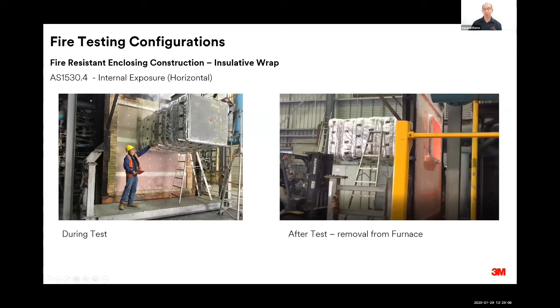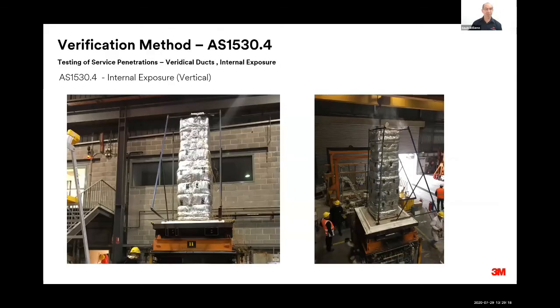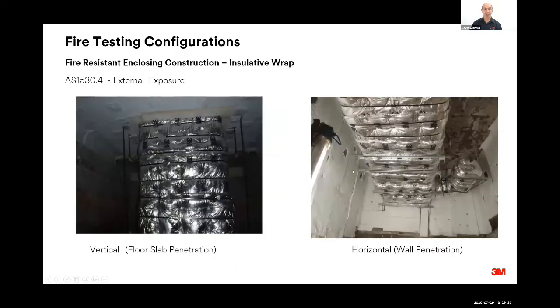And after removal from the furnace, you can see the glowing, how hot it is. Everything is glowing red hot. Just a picture here of a vertical orientation, so a duct penetrating a floor slab. And a couple of pictures showing the type of arrangement for external exposure, where the duct is built inside a furnace.